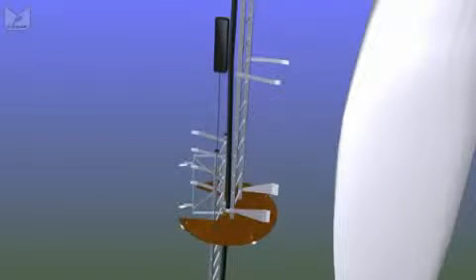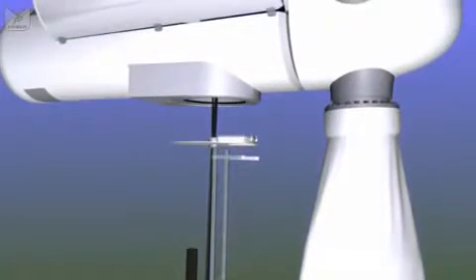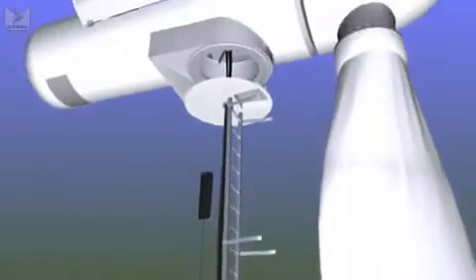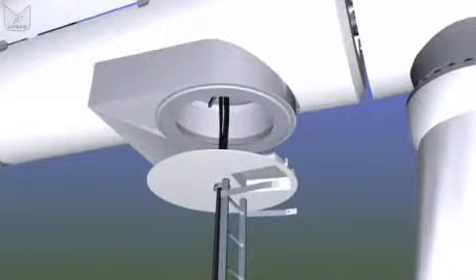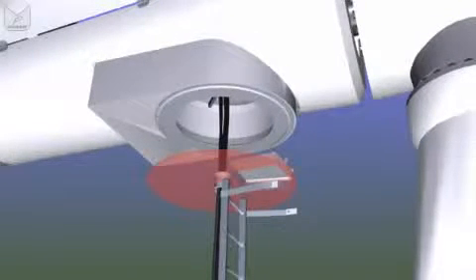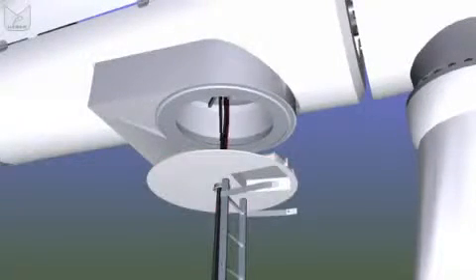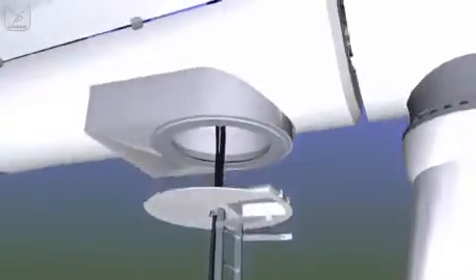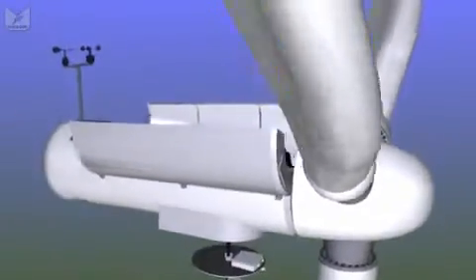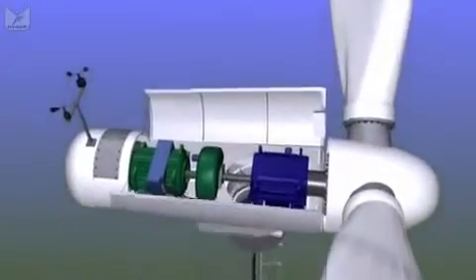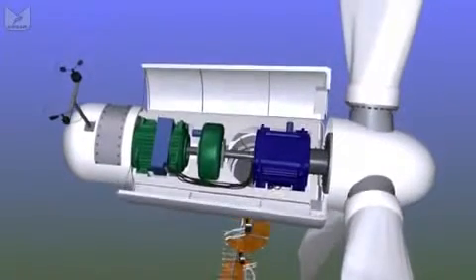But as we move up, now the cable goes through a hole in the centre of each platform, and at the top of the tower we have a steel platform with a sealed trapdoor, which we call the yaw platform. Just above that we have the yaw ring, with the bearings that allow the nacelle and the rotors to rotate around to face the wind. And this sealed platform acts as a bit of fire protection, and also avoids people falling back down the tower, because at the bottom of the nacelle we simply have a hole through which we climb.